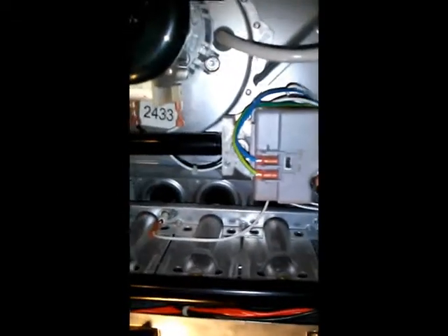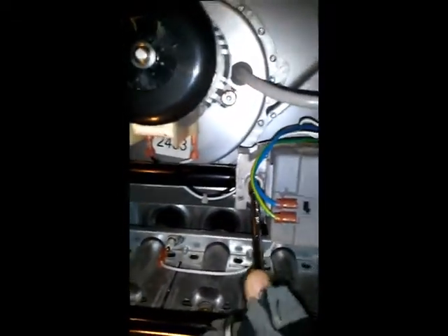So what I'm going to do now is test my gas flow through my manifold. I'm going to see if I'm sitting at 3.5, which is what we want according to this furnace, and for most furnaces that's their happy zone. We're going to double check with the faceplate here. If you can see that faceplate, it'll tell me where it wants it, which is right here, 3.5.